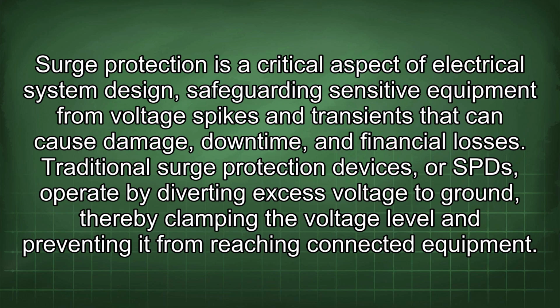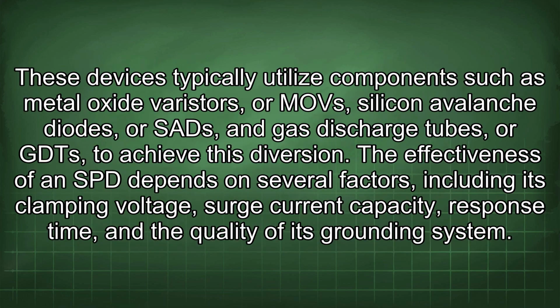Surge protection is a critical aspect of electrical system design, safeguarding sensitive equipment from voltage spikes and transients that can cause damage, downtime, and financial losses. Traditional surge protection devices, or SPDs, operate by diverting excess voltage to ground, thereby clamping the voltage level and preventing it from reaching connected equipment. These devices typically utilize components such as metal oxide varistors, or MOVs, silicon avalanche diodes, or SADs, and gas discharge tubes, or GDTs, to achieve this diversion.